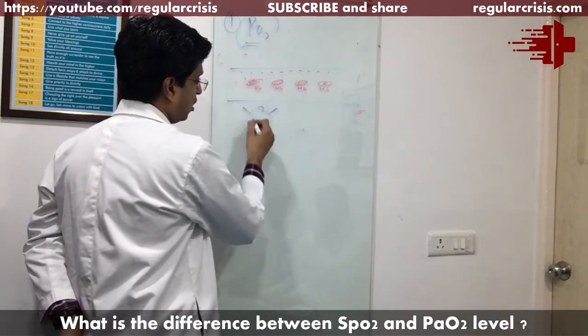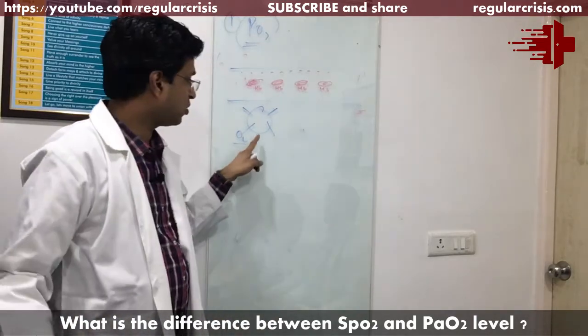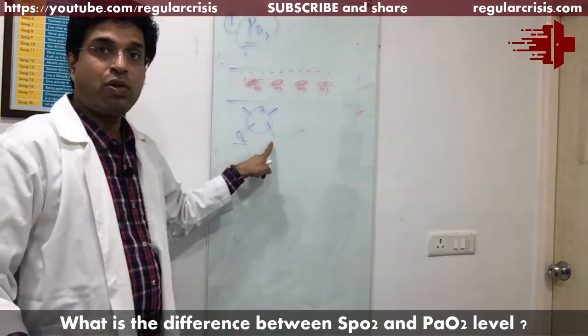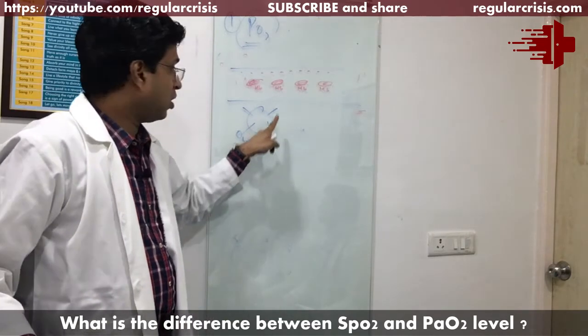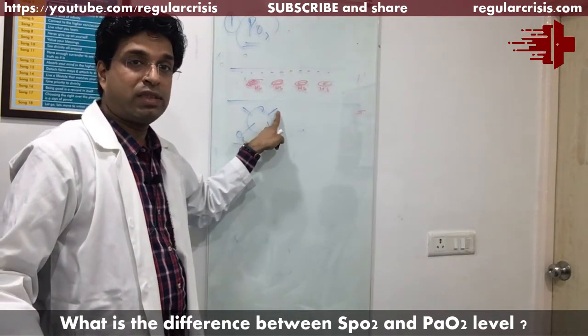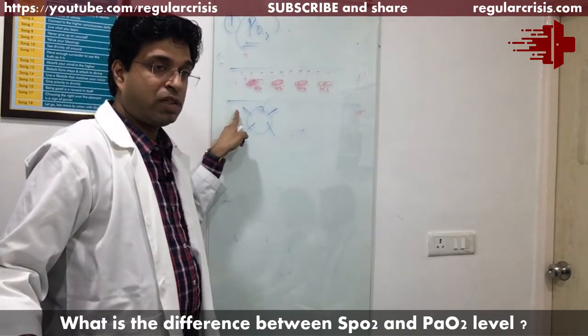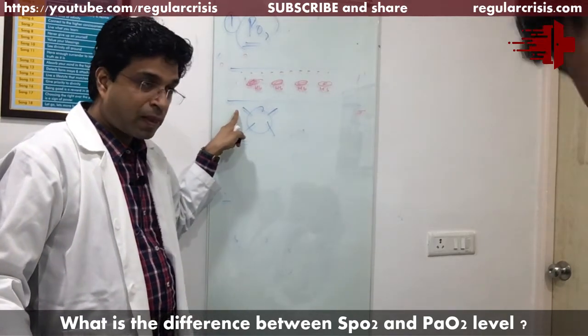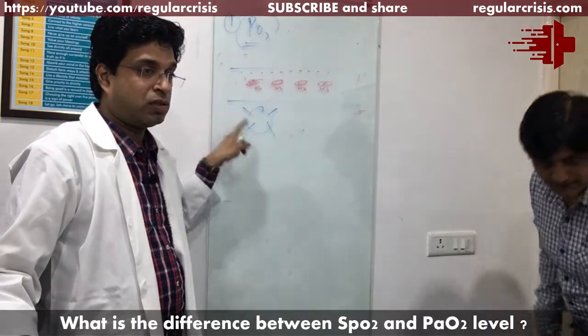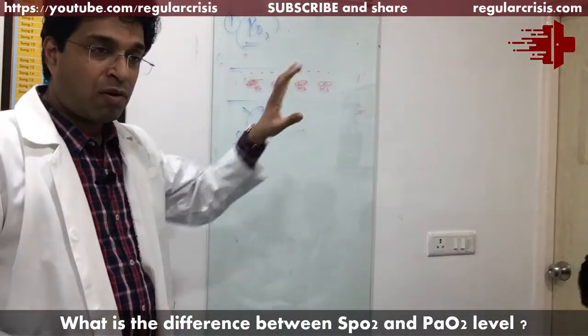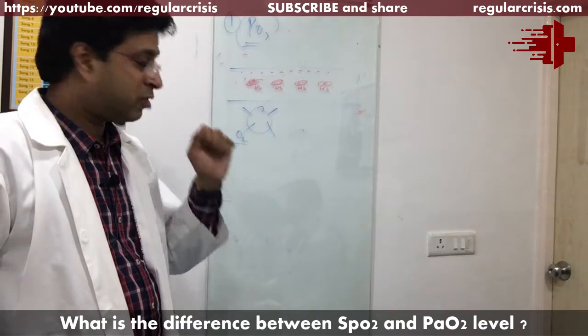Hemoglobin can carry four oxygen molecules. If there is one oxygen molecule, it is 25% saturated; two oxygen molecules means 50% saturated; three oxygen molecules means 75% saturated; and four oxygen molecules attached with hemoglobin means 100% saturated. It is the average of all hemoglobin concentration which is being saturated with oxygen that is picked up by the pulse oximeter.